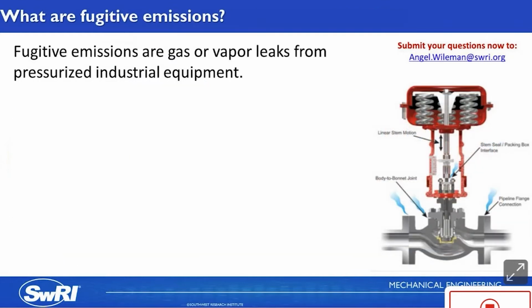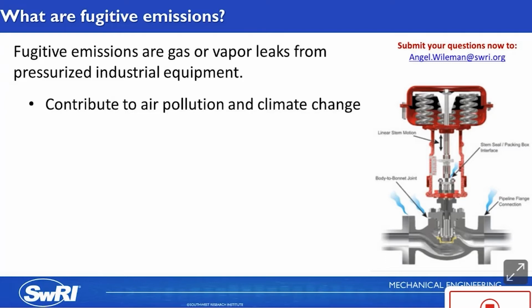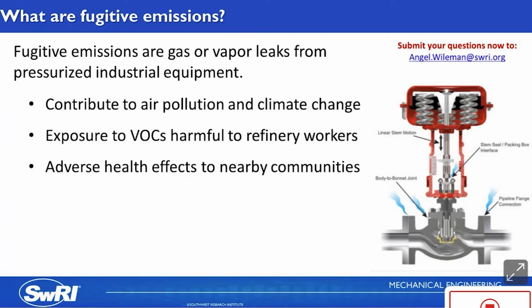What are fugitive emissions? Fugitive emissions are gases or vapor leaks from pressurized industrial equipment. The leaks are not good for air pollution and climate change. They're also not good for the health of the workers in refineries or the local community that lives next to the refineries. Additionally, the process gases are flammable, so if you have increased fugitive emissions, you're increasing the risk of site explosion. I think we can all agree that fugitive emissions are bad news and we need to minimize them. Fugitive emissions can come from any equipment, but today we're focusing on valves. And there's, interestingly, actually been some movement towards a standardized procedure for qualifying gaskets for fugitive emissions testing. But like I said, we'll focus on valves for today.